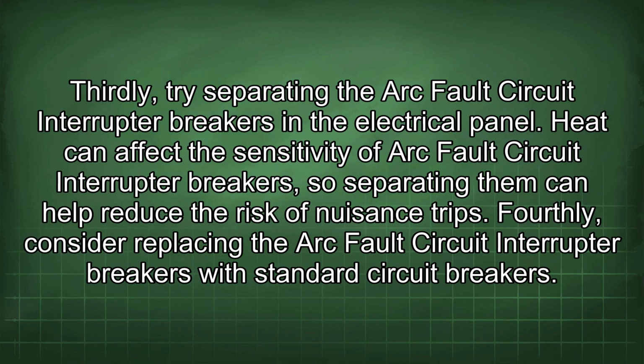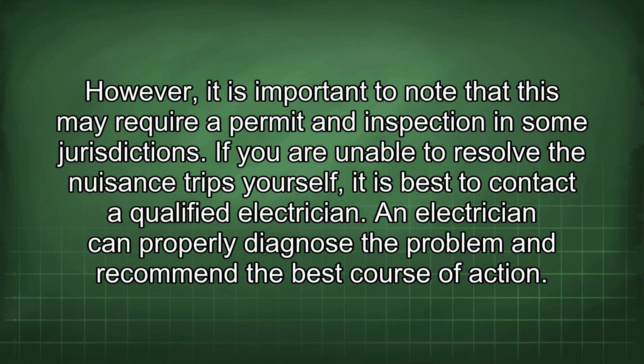Thirdly, try separating the arc fault circuit interrupter breakers in the electrical panel. Heat can affect the sensitivity of arc fault circuit interrupter breakers, so separating them can help reduce the risk of nuisance trips. Fourthly, consider replacing the arc fault circuit interrupter breakers with standard circuit breakers. However, it is important to note that this may require a permit and inspection in some jurisdictions. If you are unable to resolve the nuisance trips yourself, it is best to contact a qualified electrician. An electrician can properly diagnose the problem and recommend the best course of action.